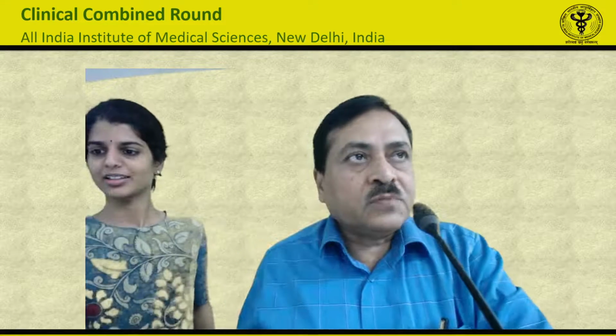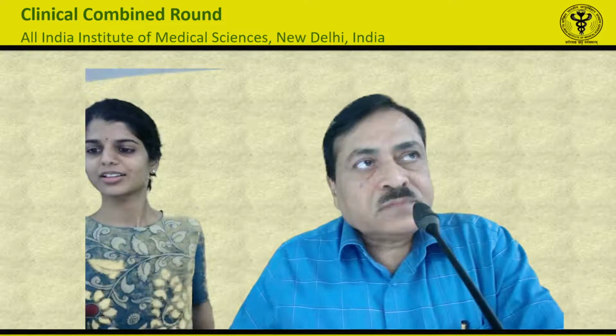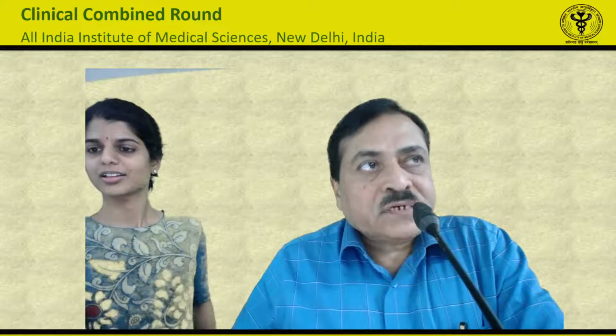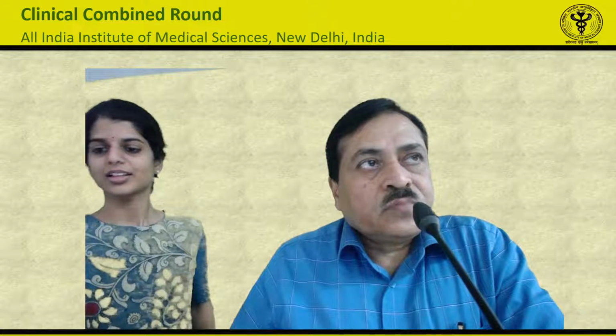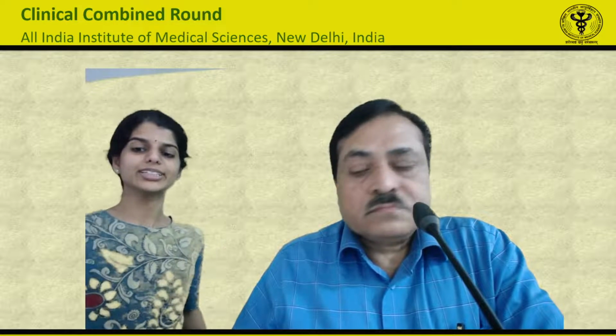Just one clarification: what I understood is Nikhila told these devices are bigger. This contour device is bigger. That's what you mentioned probably. Bigger means the size of the aneurysm. We need to have a good wall apposition, so they will adapt to the aneurysm size. There are two different sizes available, and based on the proper sizing, we select the size. With contour, it is very important to cover the neck completely.